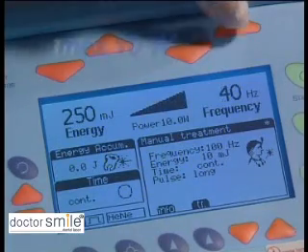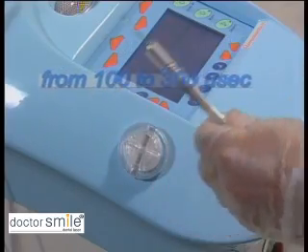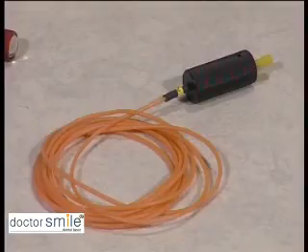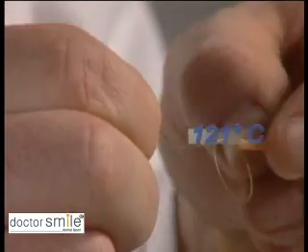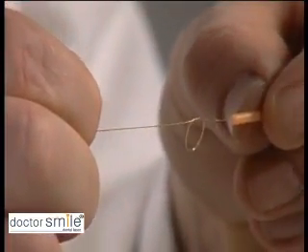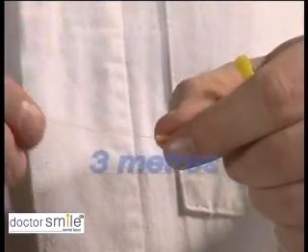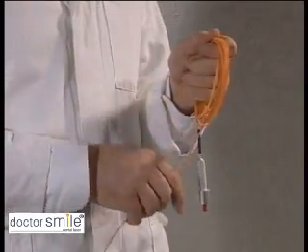The device supplies a maximum power of 10 watts with an impulse rate that varies from 100 to 300 microseconds. Optical fibers for ray transmission are flexible and may be autoclaved to 121 degrees centigrade. Diameters vary from 125 to 600 microns and with a length of 3 meters they are versatile in all applications.